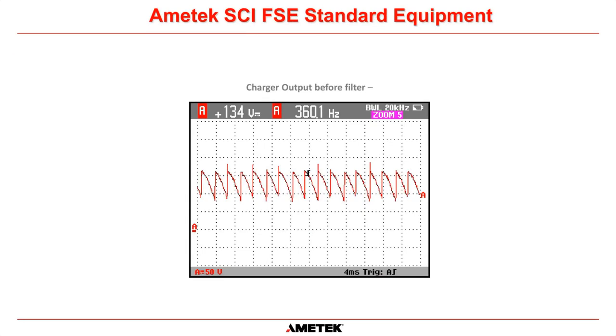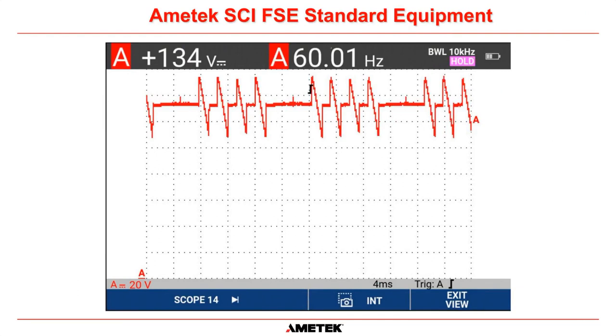And a lot of people say, well, why do you take an oscilloscope out to every visit? And it's actually critically important for a lot of the things that we do. For example, this is a healthy output of a three-phase 6SCR charger. The frequency of the output should be 360 hertz because there are six pulses per cycle for three phases. So 6 times 60 is equal to 360 hertz. And you can see that these are symmetrical. They're happening at the same time. Everything looks good on this screen, okay? But if that charger isn't working correctly, you might see an output like this. And there are actually two pulses missing here, okay? Two pulses missing here.